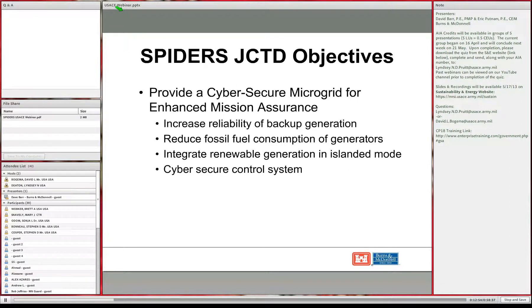As a point of reference, most utilities limit renewables to 10 to 15% of total load to maintain grid stability. Testing at 90% PV penetration was possible because diesel generators on-site are highly responsive—they can quickly compensate for voltage and frequency variations. Although people may shy away from fossil fuels, a diesel generator is a very stable, effective piece of equipment for keeping a microgrid reliable, enabling much higher renewable penetration than is possible at utility scale.